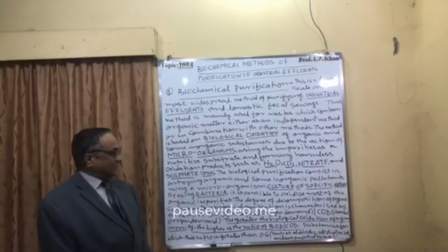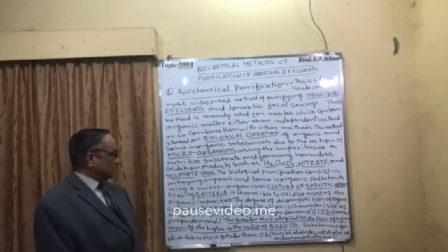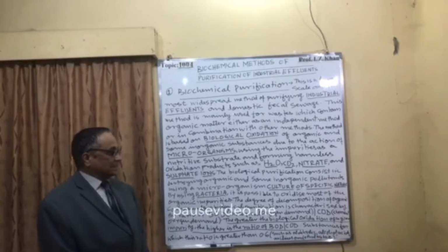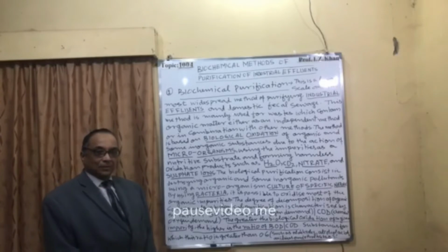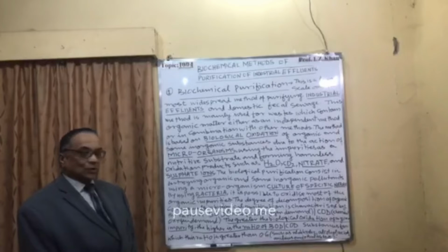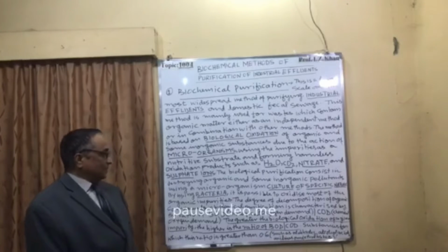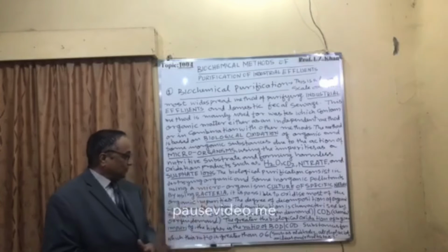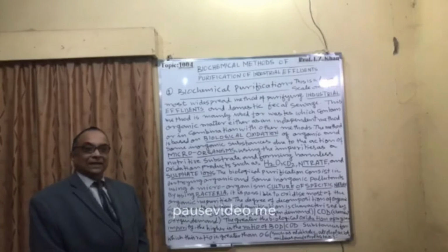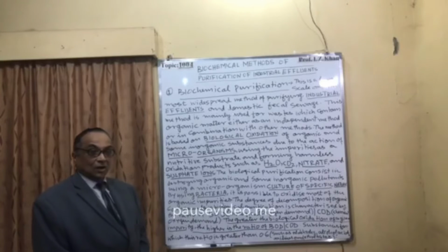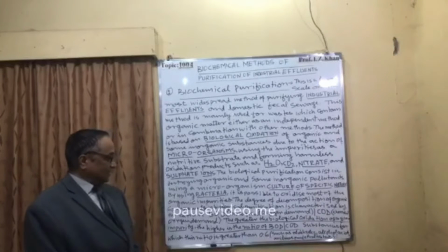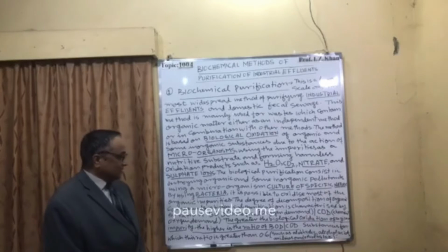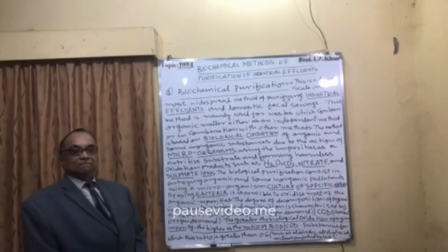The degree of decomposition of organic compounds in biological purification is characterized by the ratio of BOD, biological oxygen demand, and COD, chemical oxygen demand. This is a very important point to note: the greater the biological oxidation of a given impurity, the higher is the ratio of BOD and COD.